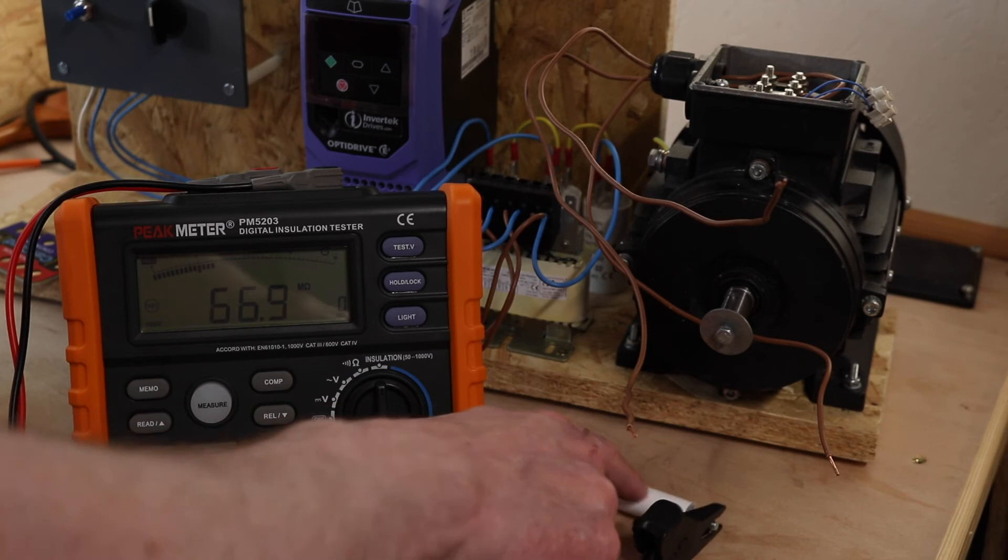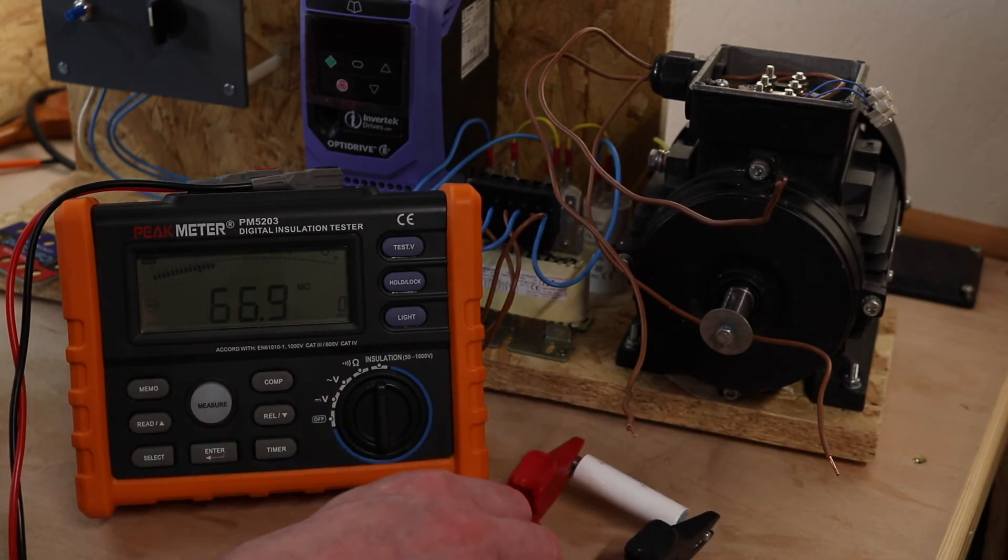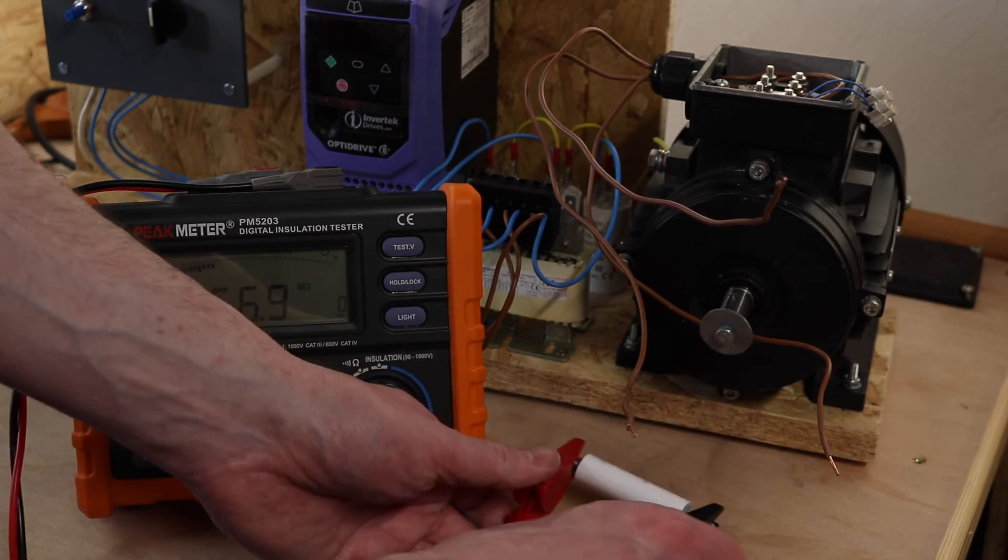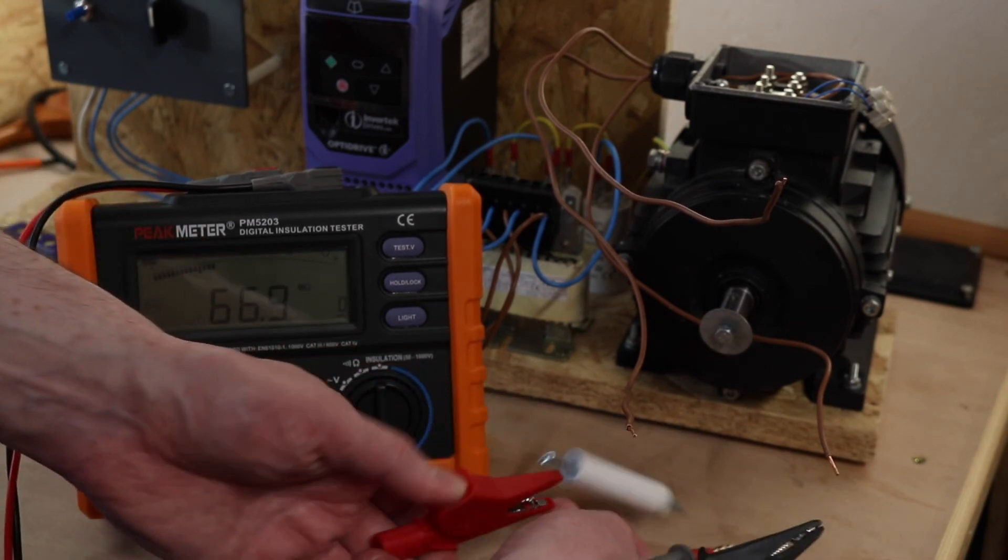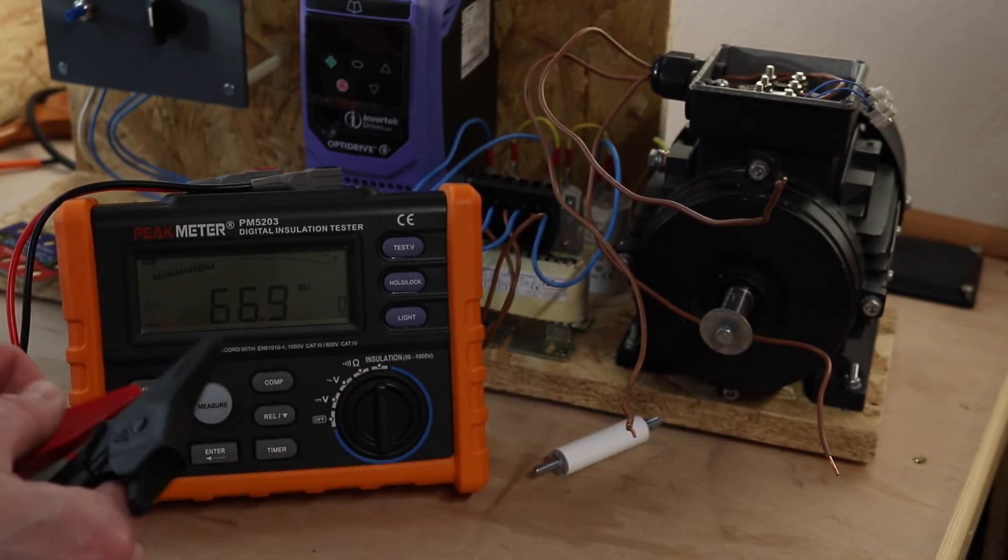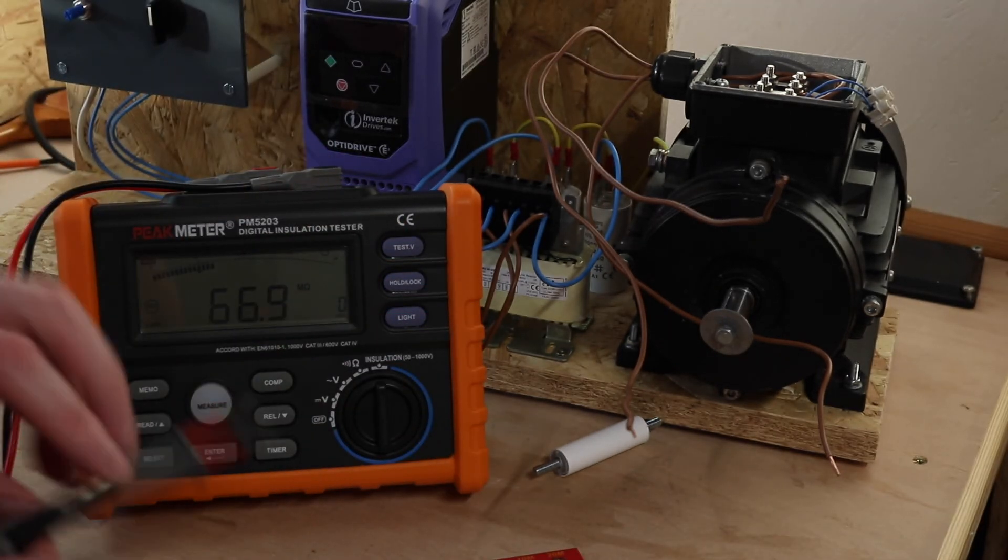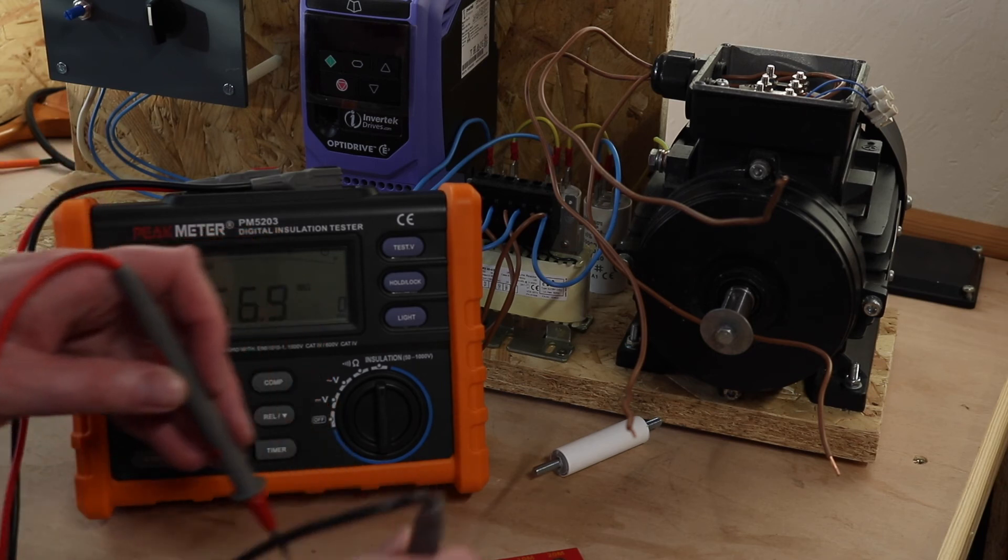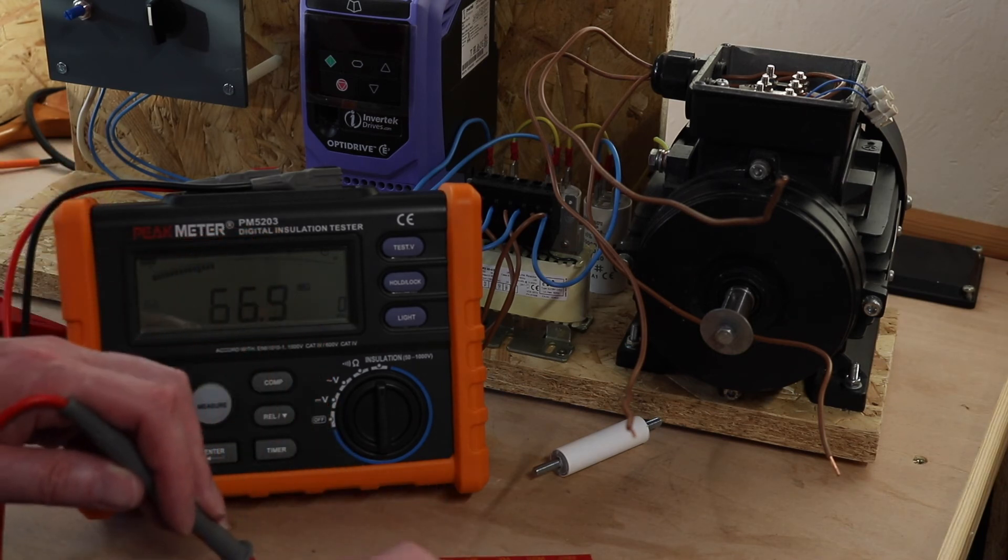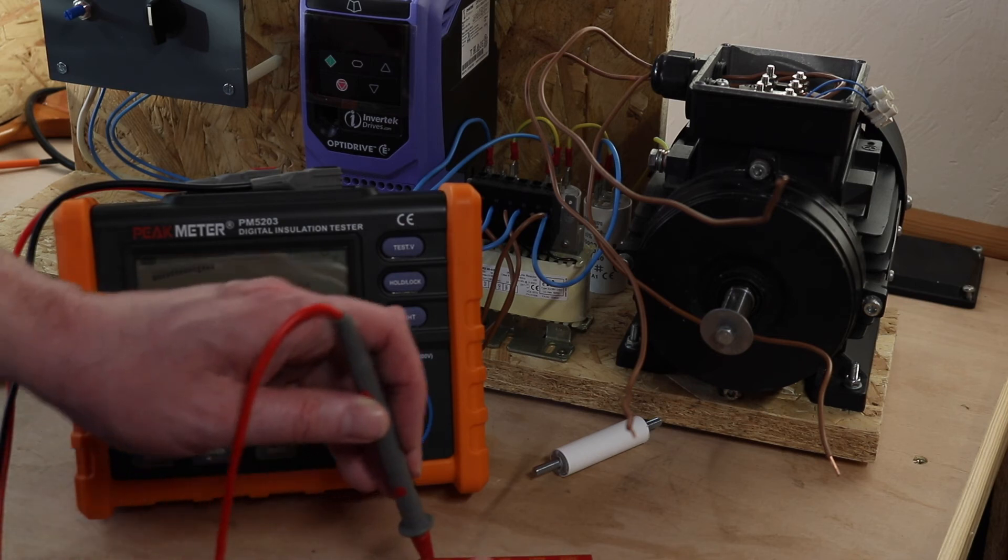A slightly more professional way of doing that as opposed to building your own up is to use something like the cal card here. These are widely available in the UK. I've got five various resistors here from 0.5 to 20 mega ohm, and I can just put the probes across this, be the 20 mega ohm.